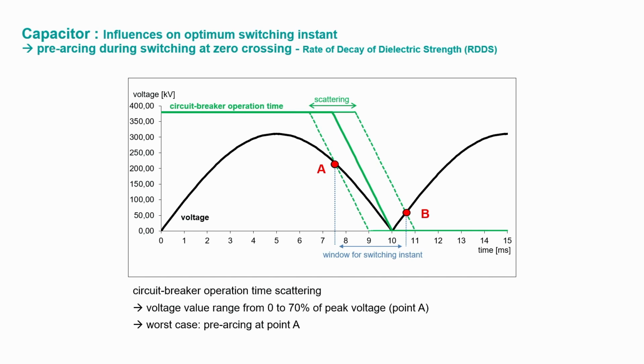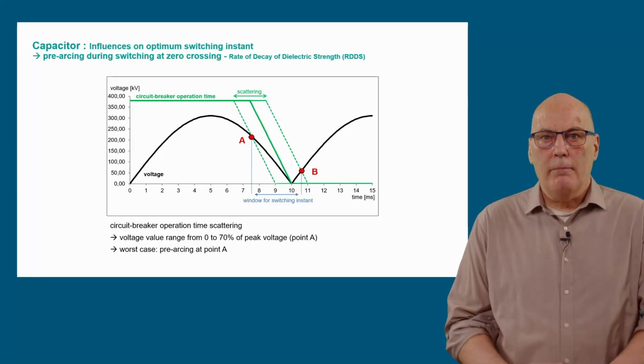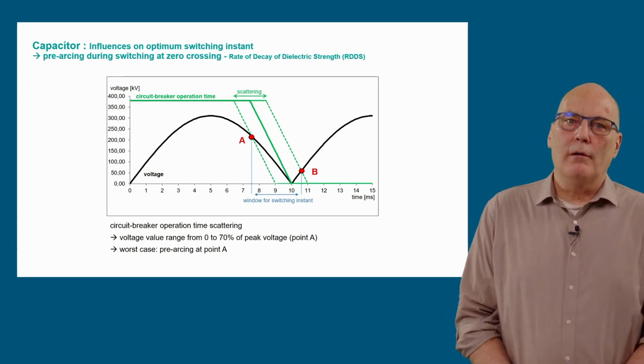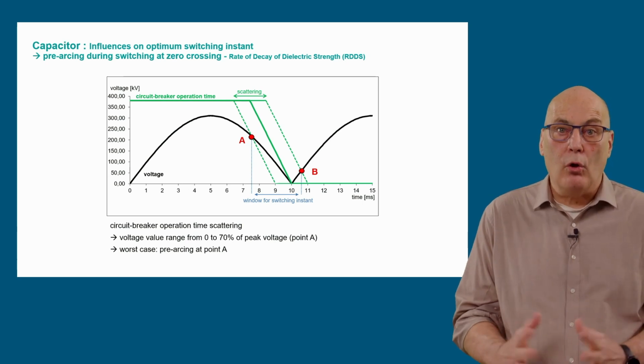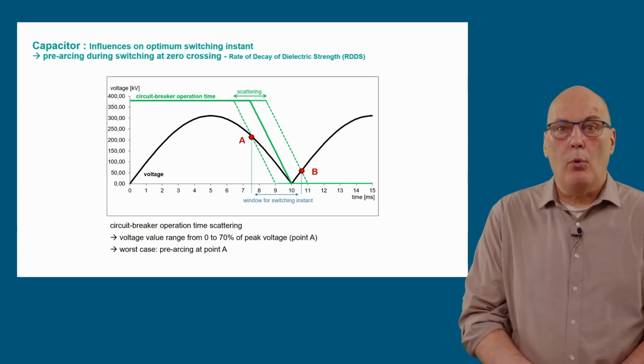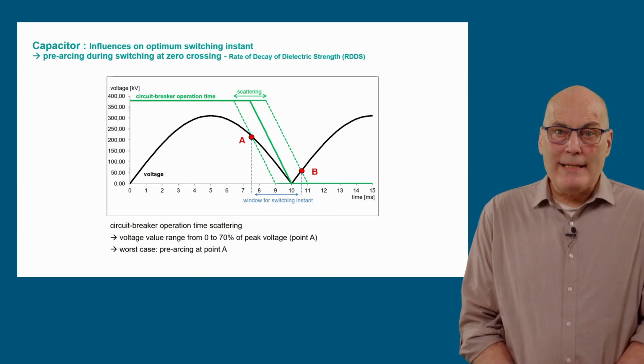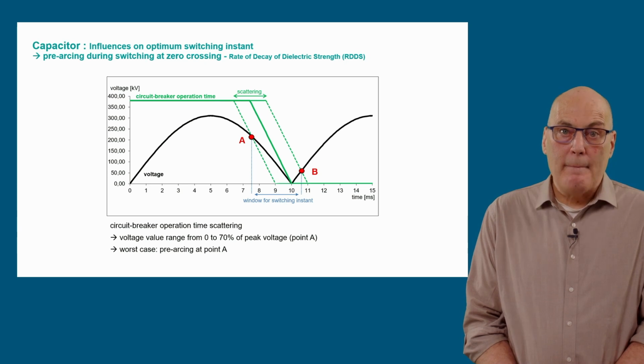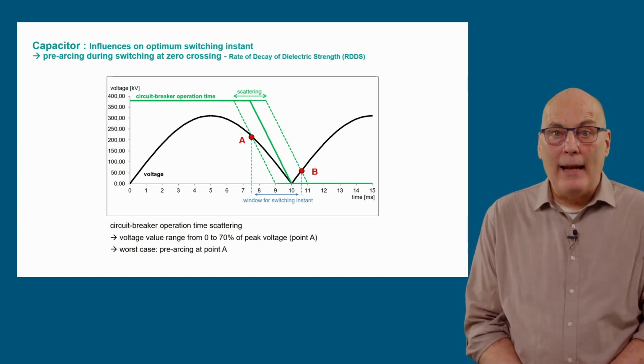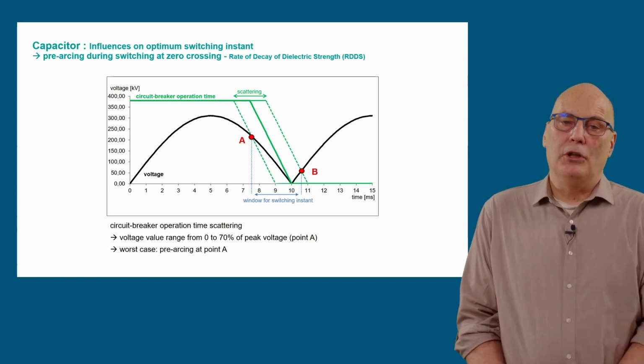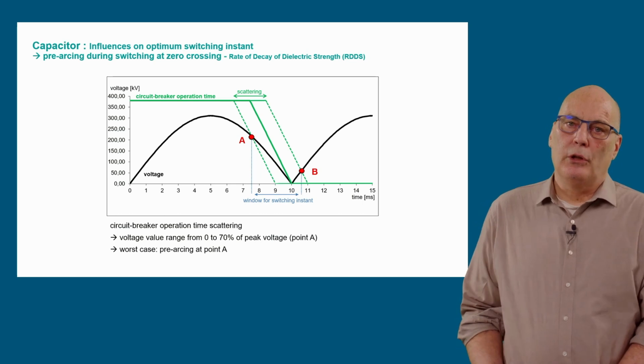For near zero voltage capacitor bank closing, it may be necessary to check the RDDS curves. The circuit breaker will not always close with exactly the predicted speed, even if all influencing factors are considered. There will be some scatter in the operating times. In this diagram, it is shown that the extremities of the scatter will result in make time termination, electrical contact, at point A earliest and point B latest. For a capacitor, point B is okay, close to zero, but point A is bad as it is at 70% of peak voltage. This can be improved as shown on the next slide.